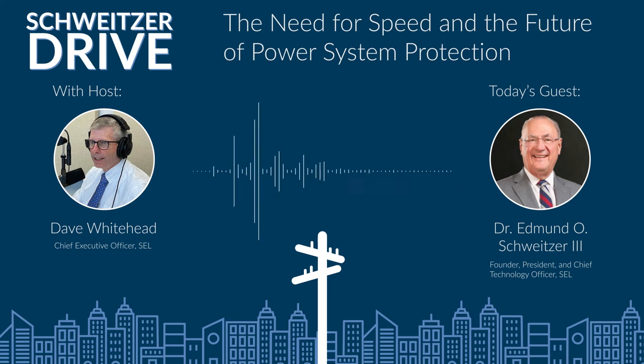So it's slower. It's a millisecond for a signal to get from Dave to me and me to Dave. So we're really at about 1.3 milliseconds is the theoretical limit at this point in time, if you pardon the pun here. That's about where we are. And I think we can get a little bit faster by using some of the traveling wave distance ideas. But where we are right now is we're limited for speed by the line length. If you want to trip any faster, well, you have to move the relays closer together.